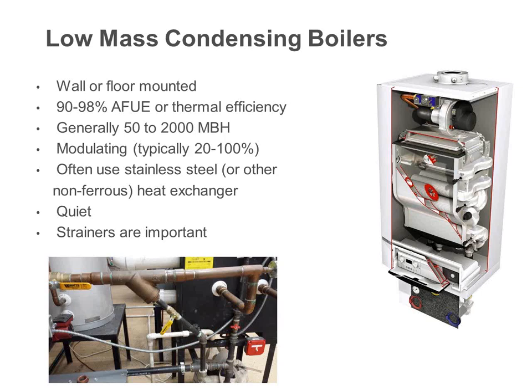Most boilers do modulate on a 5-to-1 turndown rate. Since we are condensing, we have to use materials that will deal with it. This condensate is corrosive. So basically, stainless steel is one of the most popular, copper, nickel, or aluminum. These boilers also are a lot quieter than the old days. One thing we do when you talk to us about a boiler is we will make sure on these low mass boilers, since the tube passes are very small, that we will provide you with strainers. Very, very critical.